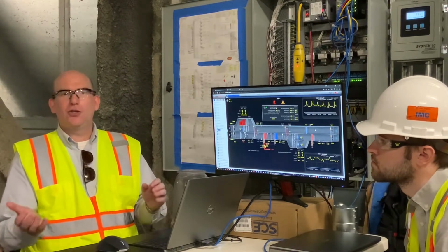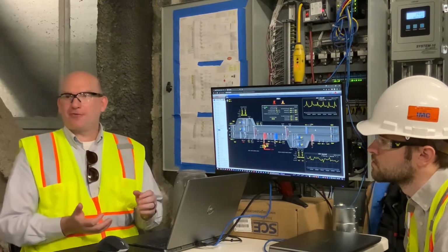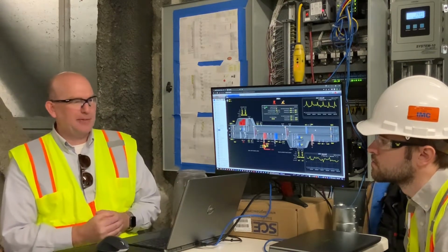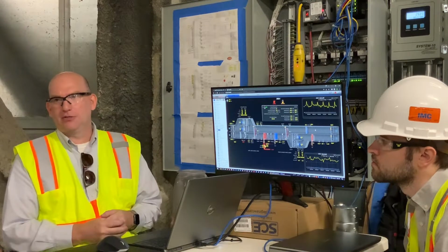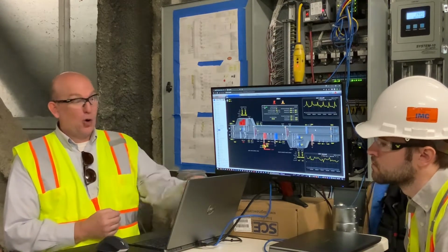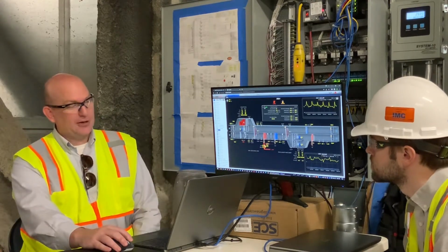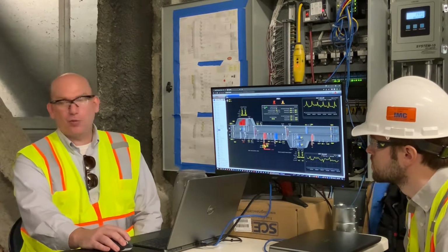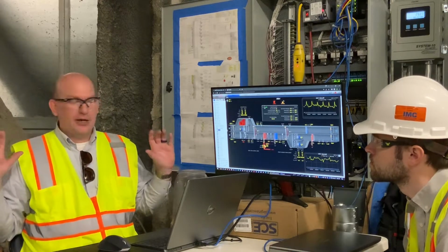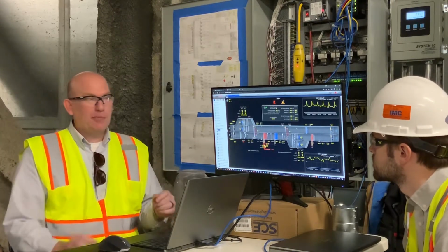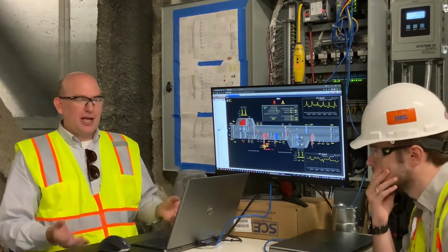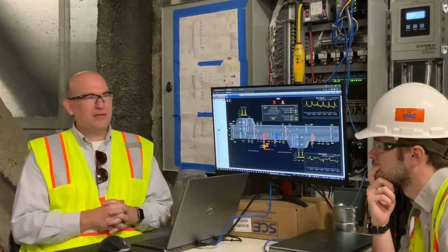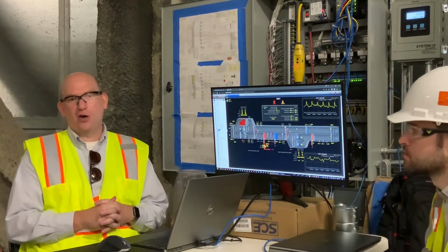Obviously, we all know you can have a damper that seizes up, you can have a bad actuator, so the potential still exists for it to happen, but it's not going to happen because of the controllers. If the VFD shuts down, both VFDs, like we have one faulted out here right now. If the second VFD shut down, the entire unit would shut down, and we would close off all 4 points. Okay? So that's important both on the shutdown sequence as well as the startup sequence. So when a unit starts up, it also means that the fans have to start before we open those dampers.